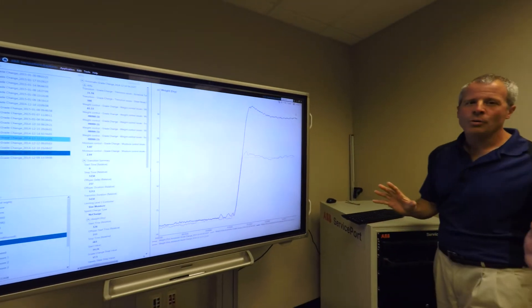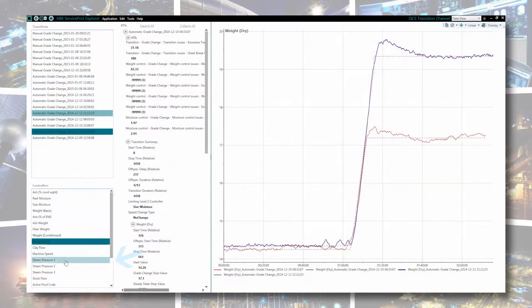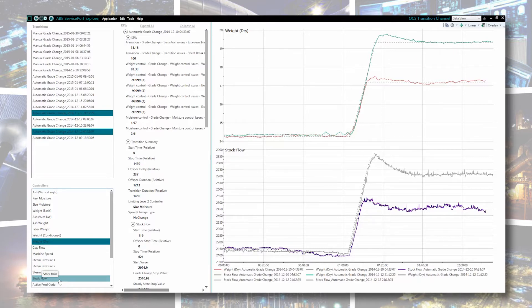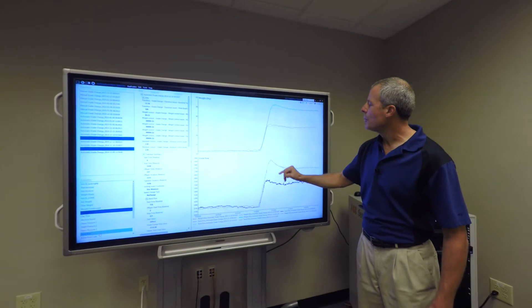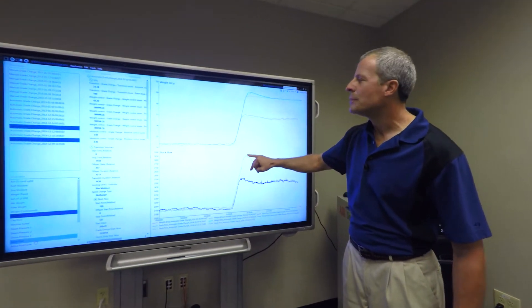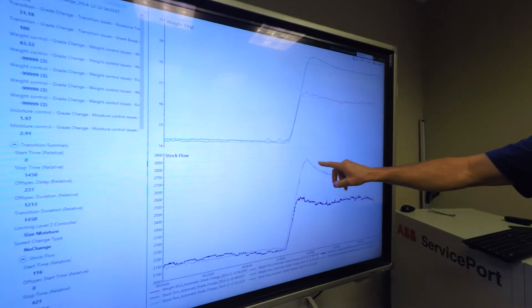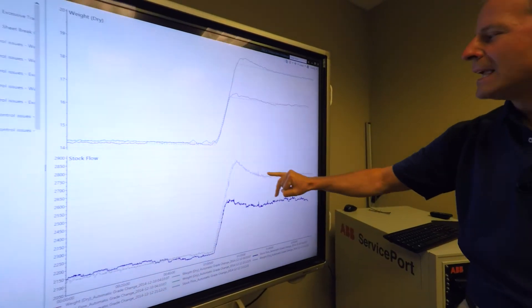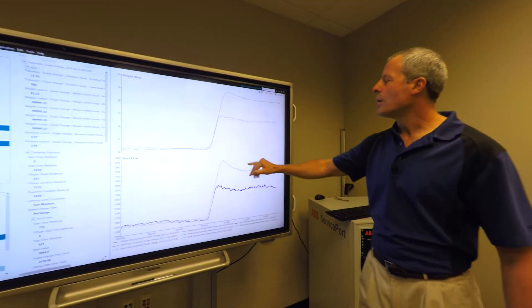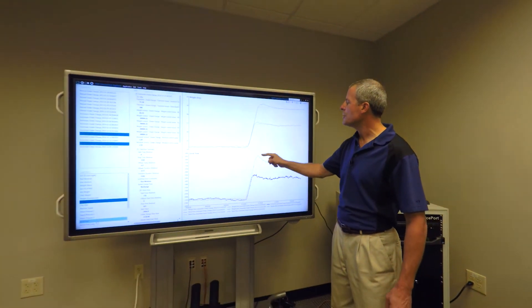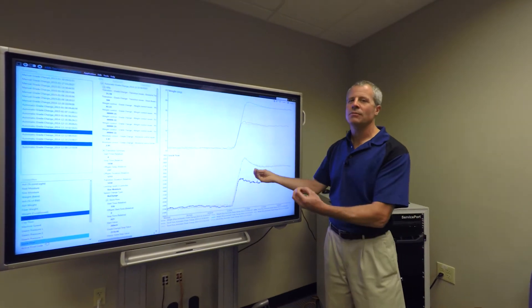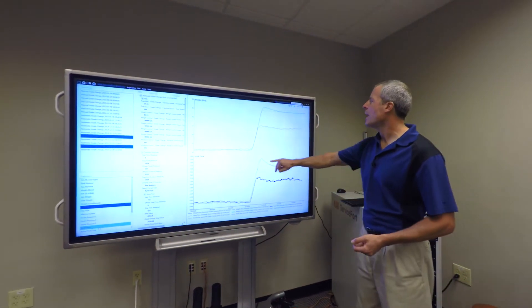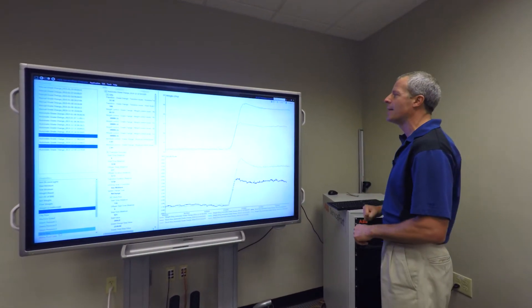Let's look at the stock flow level one or the DCS PID for stock flow. In addition to looking at the weight change for these two transitions, now we're looking at the stock. You can see the one change on the stock flow where we actually went up to close to 2,900 GPM. Notice that where the transition went to versus where we end up, those are two different places. Part of the feedforward feedback that occurs during the transition, there could be a modeling update. Right now we've identified a potential area for improvement for the stock flow modeling just based on these two transitions.